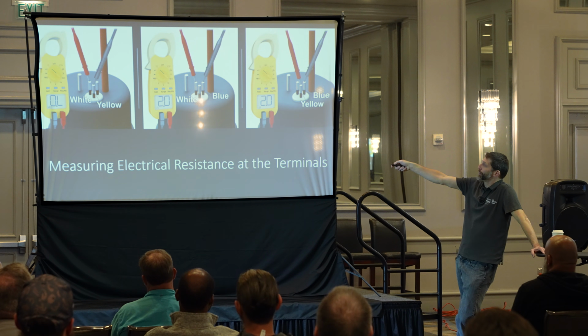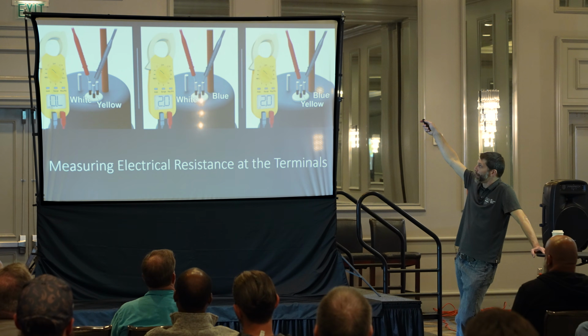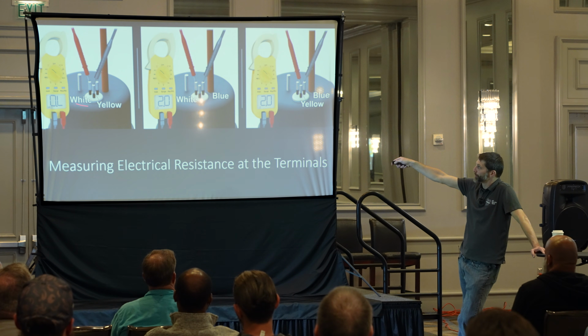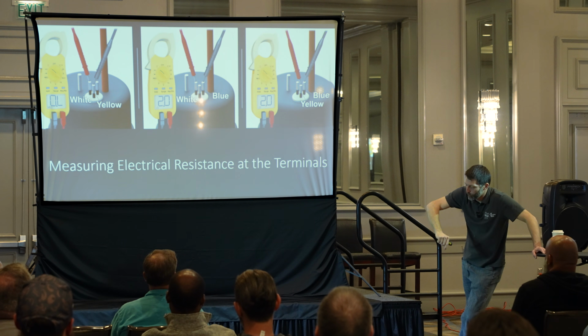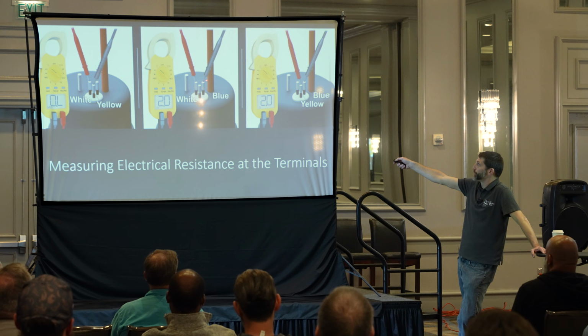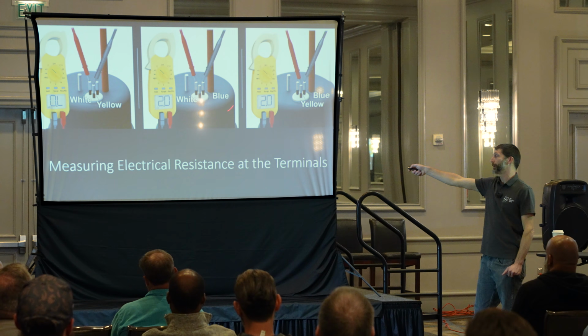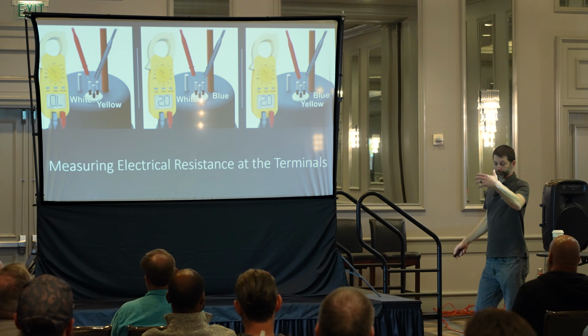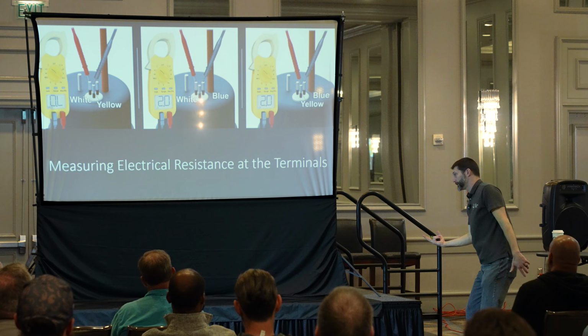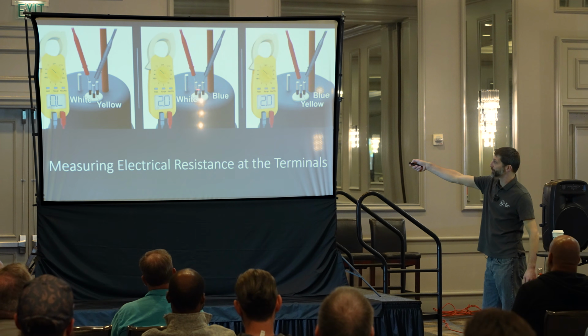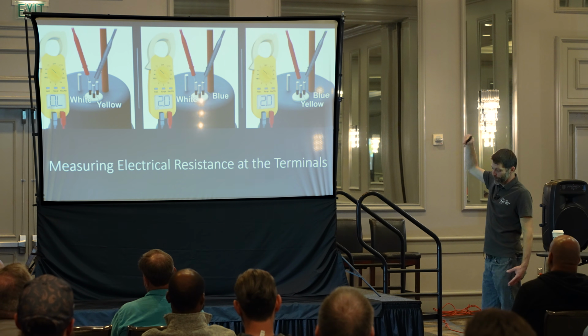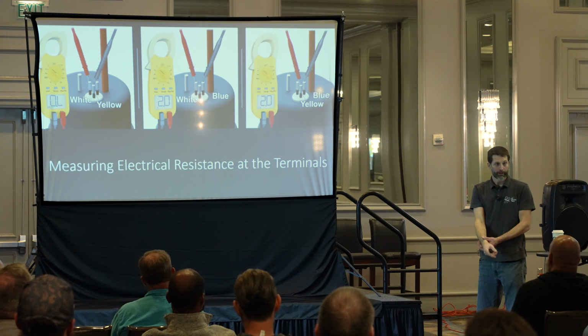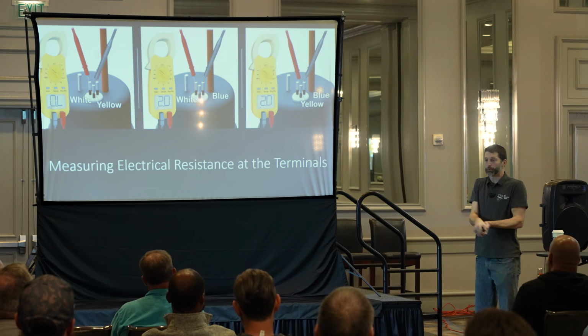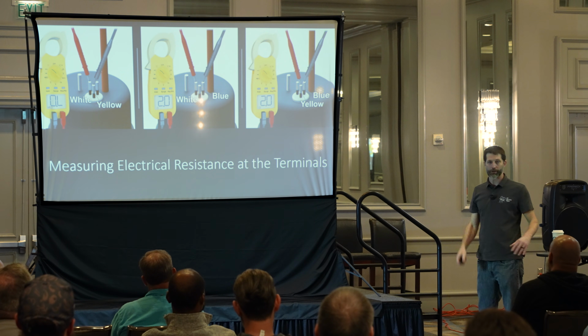Anyway, if you read OL at the prior spot, then you're going to open up the disconnect, open up the wiring harness area over here in order to then pull your wires off of the spade terminals. By the way, this is the weakest part of the entire system. On single speed systems and on mini splits, this is the area where the electrical wires go into the pressurized cabinet. If you yank on these and twist them and pull, you could have refrigerant blow out.